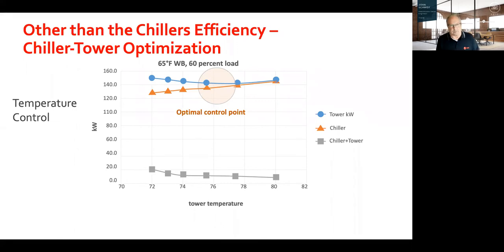And in this example, we have a 65-degree wet bulb temperature, and the plant's running at 60% load. Well, you might think colder's better, so let's drive that tower down to 72 if we can get it. But the reality is, by looking at both chiller and tower efficiency and optimizing how much fan energy we were using versus how much chiller and pump energy we're using, the sweet spot in this particular case is around 76, 77 degrees of condenser water temperature.